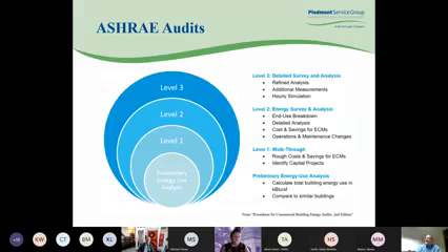So ASHRAE gives us some guidelines for audits. A preliminary audit gives us rough estimates of kW per square foot. How does that compare to other facilities or other industries? A level 1 audit, we go in and take that basic audit and expand on it. It's designed to give businesses a starting point for making changes or further in-depth auditing. We use it to interview key people and review facility bills and prepare for a level 2.